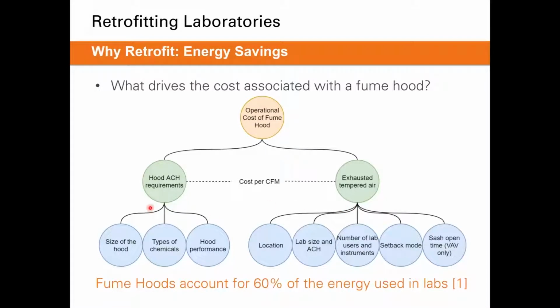So for hood ACH requirements, what things affect this number would be the size of the hood. So if there's a larger hood, you would need more air in order to maintain the ACH requirements. The types of chemicals being used in the hood. So if you have something that is of a higher concentration, or if you're doing tests with flammable chemicals in the hood, that might drive up your ACH requirements for that hood, your air change rate requirements.